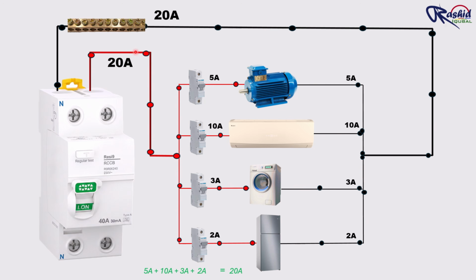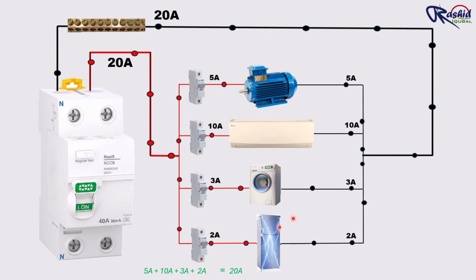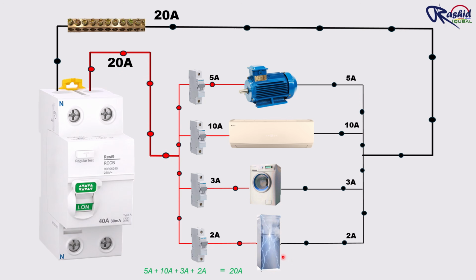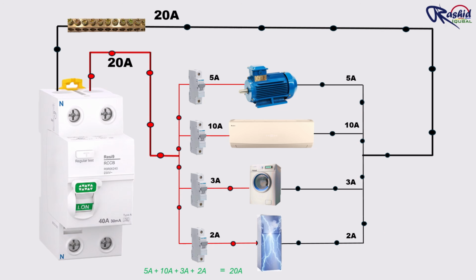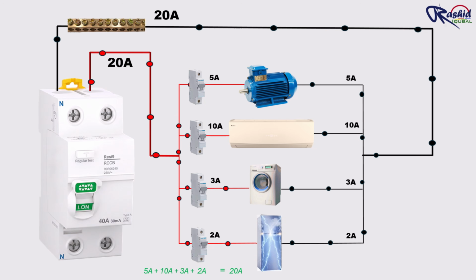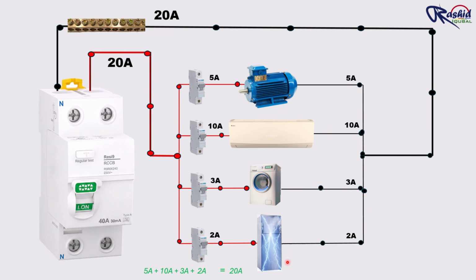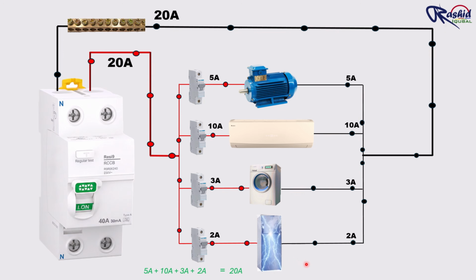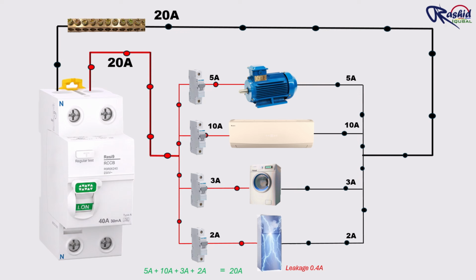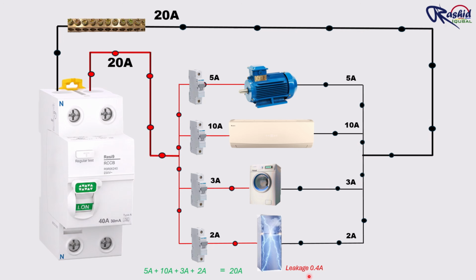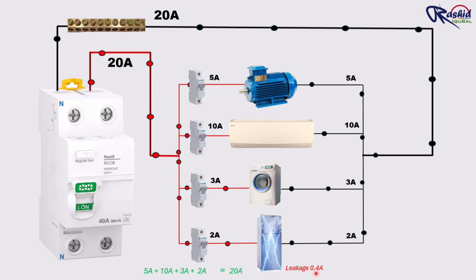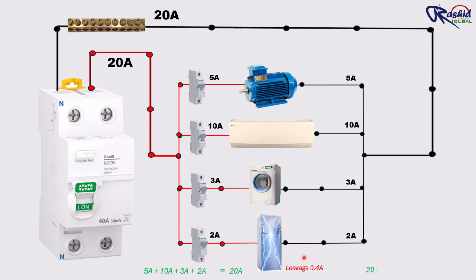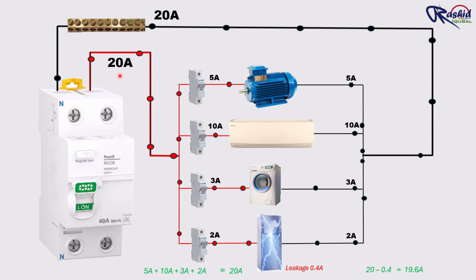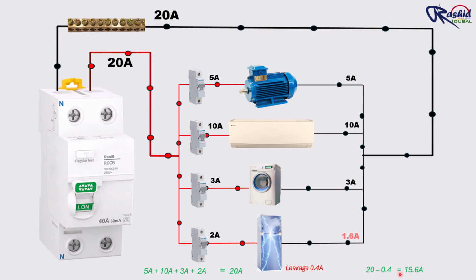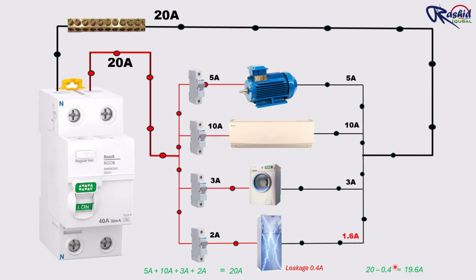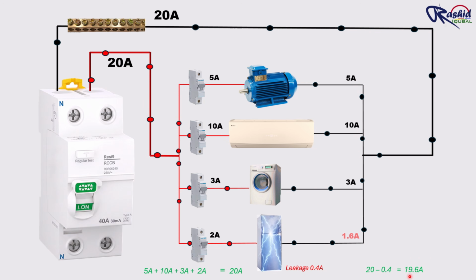Now let's see what happens during an earth leakage fault. Suppose the insulation inside the refrigerator gets damaged and the phase wire touches the metal body of the refrigerator. Now the metal body becomes live and some current starts flowing through the earth instead of returning through the neutral wire. For this example, let's assume the leakage current is 0.4 ampere, which is equal to 400 milliamps. Now the current through the phase wire is 20 ampere and the current returning through neutral is 20 minus 0.4 ampere, equal to 19.6 ampere. This is the current flowing through neutral after leakage.